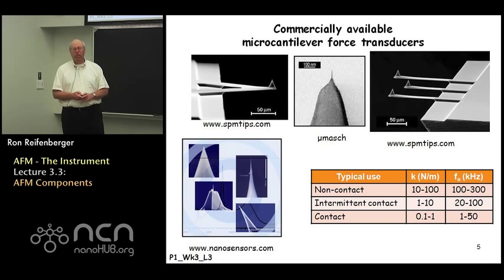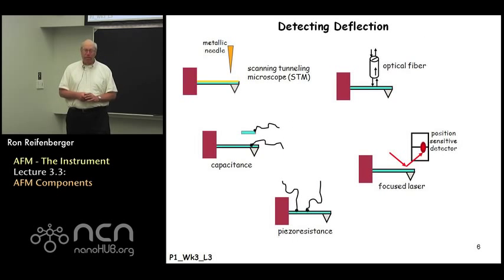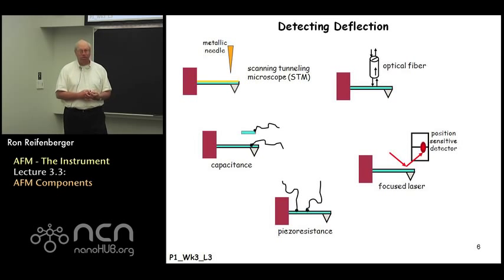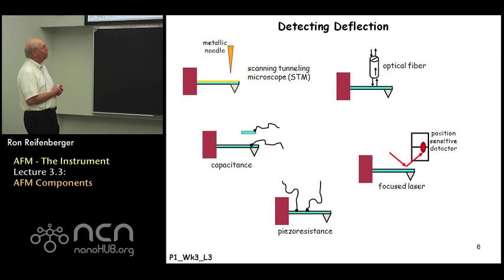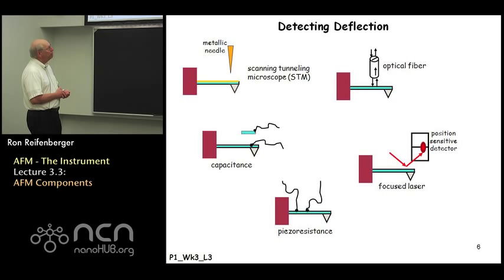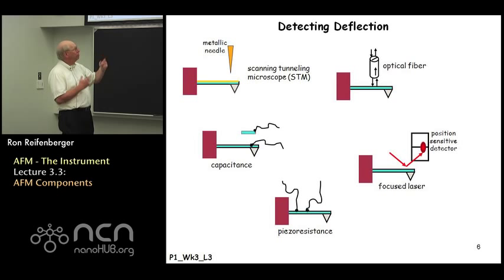The cantilever is the restoring spring in the atomic force microscope. It then becomes important to be able to detect the deflection of that spring, and a variety of techniques have been proposed to do that. Of these approaches, the one using a focused laser beam reflecting onto a position-sensitive photodetector is by far the one that has achieved the most use. A lot of our discussion in the remainder of this course will be designed to understand the physics and optics associated with that focused laser means of detecting the deflection of the cantilever.